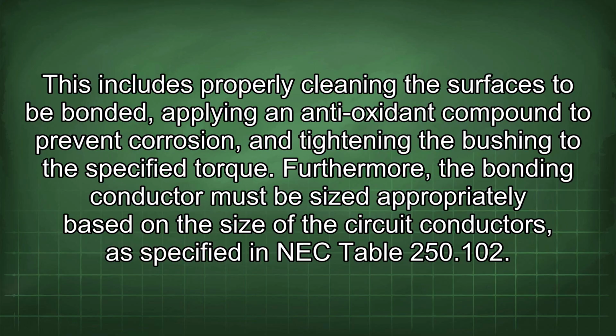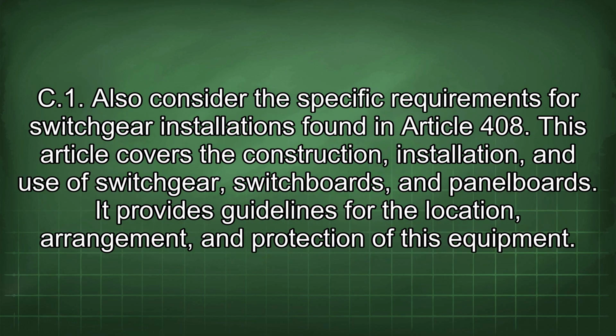Furthermore, the bonding conductor must be sized appropriately based on the size of the circuit conductors, as specified in NEC Table 250.102(C)(1). Also consider the specific requirements for switchgear installations found in Article 408. This article covers the construction, installation, and use of switchgear, switchboards, and panelboards. It provides guidelines for the location, arrangement, and protection of this equipment.